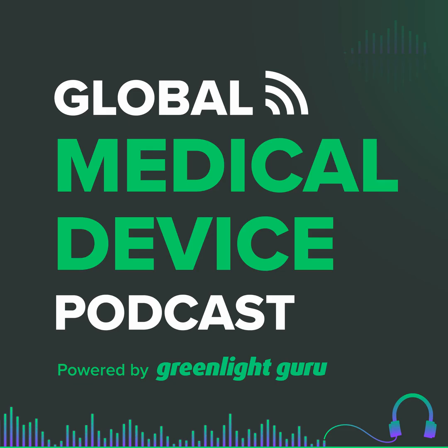For example, one customer asked me recently, can we include in our 510K a change that we anticipate making in the future? However, we don't know all the details of that change yet. Well, I said to them, look, put yourself in the FDA's shoes. If I say to you that here's my medical device, it's going to do X, Y, and Z today. Tomorrow, it might also do A, B, and C. Can you please approve that? How can they possibly do that without knowing exactly what those changes are? And more importantly, how can they do that without having the data in advance to support those changes, even though you have not implemented them yet? So I think there are a lot of potential advantages to the PCCP, including for non-software devices, but there are some challenges as well.